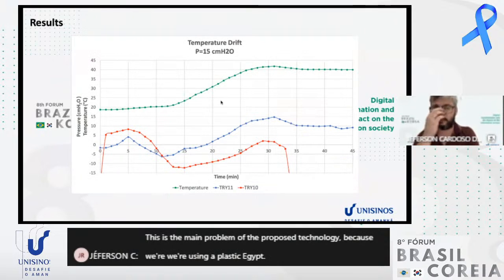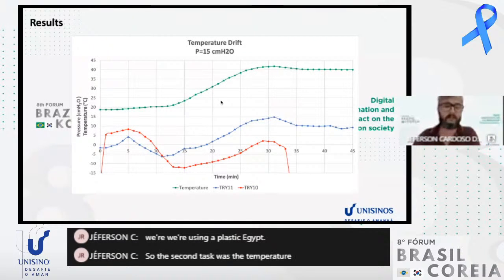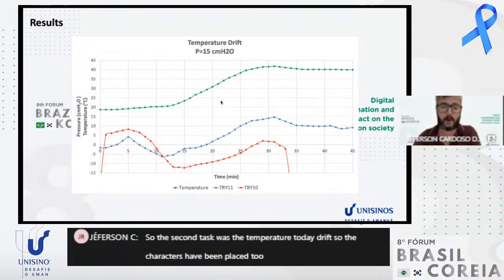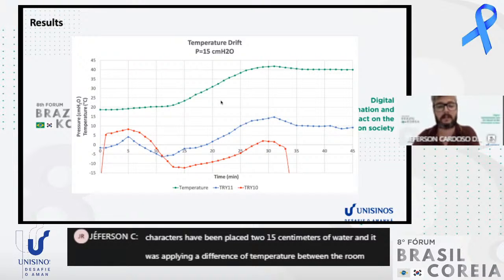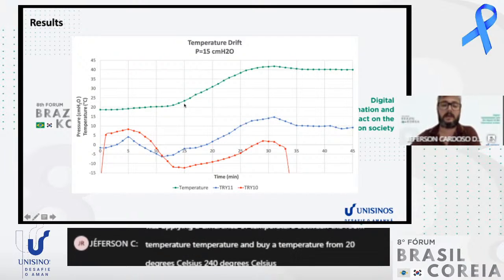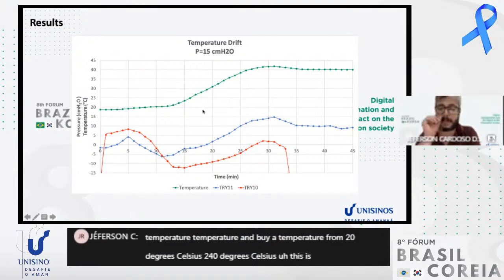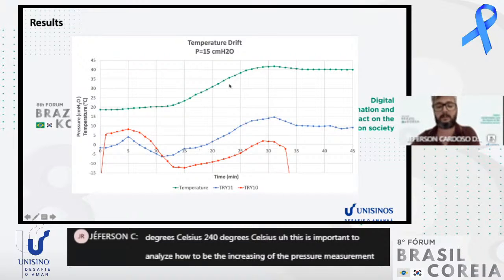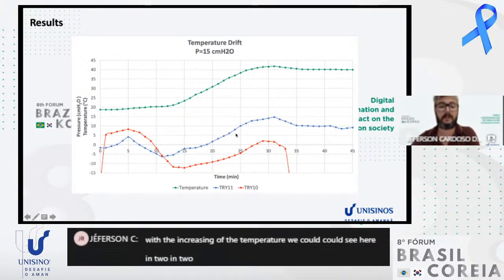So the second test was the temperature drift. The catheters have been placed at 15 centimeters of water, and we applied a difference of temperature between room temperature and body temperature, from 20 degrees Celsius to 40 degrees Celsius. This is important to analyze how the pressure measurement increases with increasing temperature. We could see this in two different prototypes.